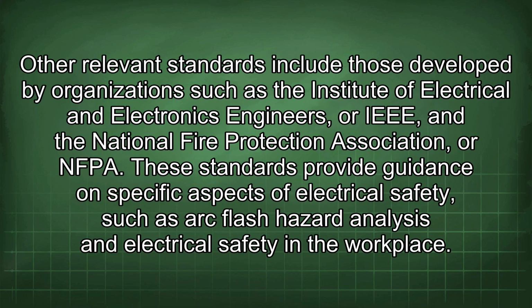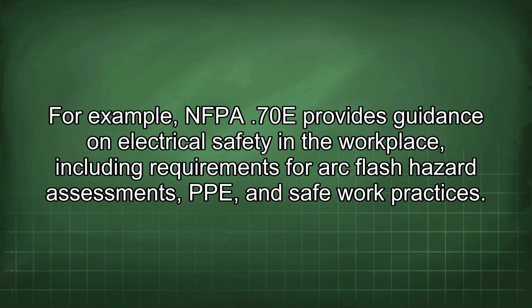Other relevant standards include those developed by organizations such as the Institute of Electrical and Electronics Engineers, or IEEE, and the National Fire Protection Association, or NFPA. These standards provide guidance on specific aspects of electrical safety, such as arc flash hazard analysis and electrical safety in the workplace. For example, NFPA 70E provides guidance on electrical safety in the workplace, including requirements for arc flash hazard assessments, PPE, and safe work practices.